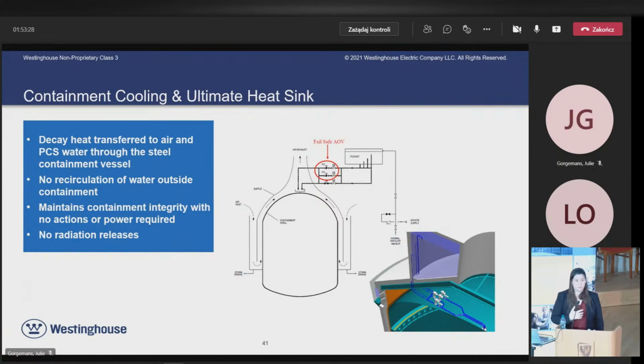We simply pour water on top of it. That water flows down the sides of the containment vessel, evaporates, and removes heat from inside containment. It's really simple, and we only make the tank big enough for 3 days of pouring water on top of containment. So inside containment, everything is taken care of. We isolate containment when we're in passive safety mitigation, and use our passive containment cooling systems to remove the heat from inside.